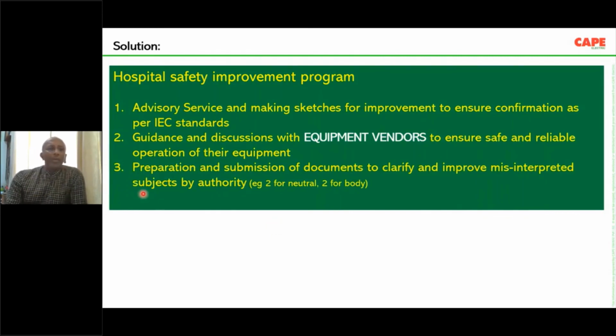And the third thing which we do is the preparation and submission of documents to clarify and improve misinterpreted subjects by the authority. What I mean by authority is, sometimes the electrical inspector, they will say, I want 2 earth pits for neutral, 2 earth pits for body, 2 for DG, 2 for DG neutral, and so on. Actually, as I said, this is wrong. This is never written in the standard. These are misinterpretations of the standards and regulations. So we also support the client in discussing or making such things perfect, and also do inspection and testing. So this is all about safety.